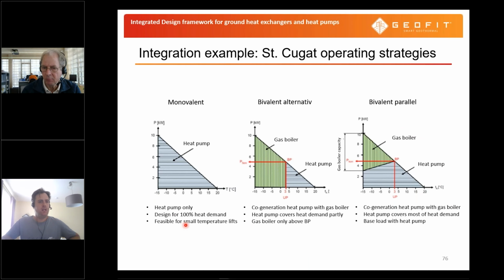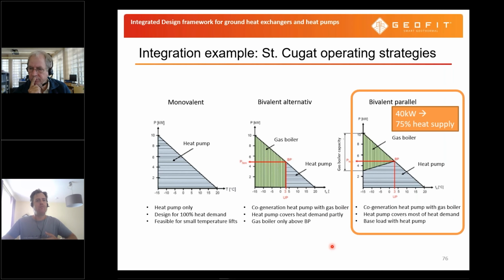You can do it either by the heat pump alone, in either-or operation, heat pump or gas boiler. But of course, in terms of efficiency and heat pump usage itself, parallel operation is favorable. Yeah, that you do the base load with the heat pump and just fire up the gas boiler when it's needed for really cold days. So in the end, with this bivalent parallel operation, with a 40 kilowatt heat pump you can go beyond 75% heat supply. Yeah, so you don't need to cover those installed 200 kilowatt gas capacity.